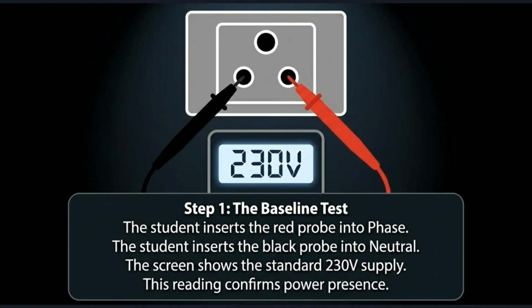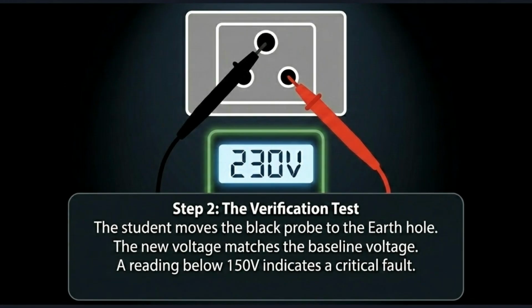Step 1 is the baseline test. Insert the red probe into phase and the black probe into neutral. The screen should show the standard 230-volt supply, confirming power presence. Step 2 is the verification test. Move the black probe to the earth hole. The new voltage should match the baseline. A reading below 150 volts indicates a critical fault.